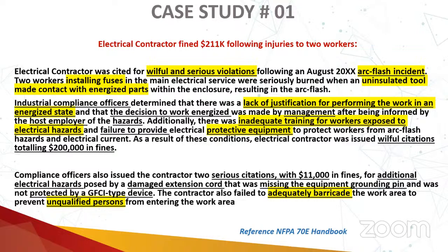There is also a misconception in the industry that arc flash only occurs at high voltage levels. No, it's a myth. It's not very well understood. Arc flash hazard can occur if we are working at above 50 volts. As per NFPA 70E, 50 volts is the threshold for deciding whether an electrical hazard is present or not. When we talk about electrical hazard, it covers both shock hazard and arc flash hazard.